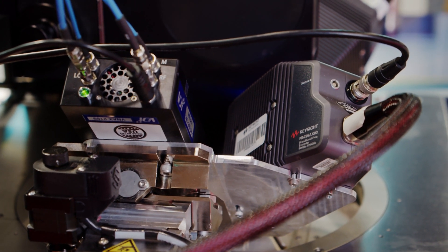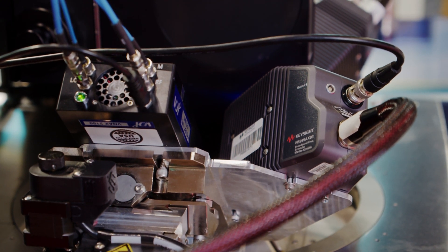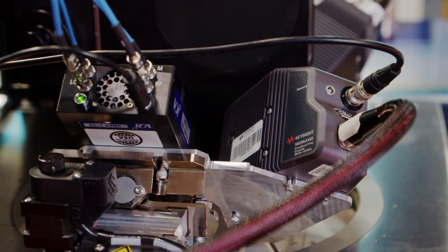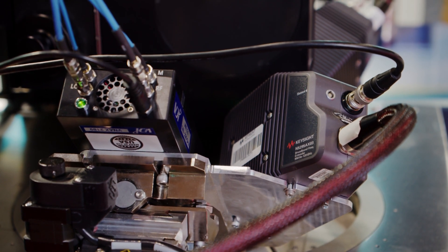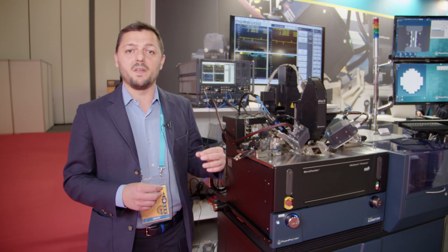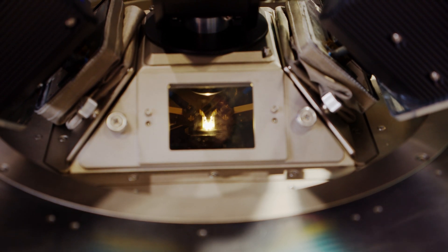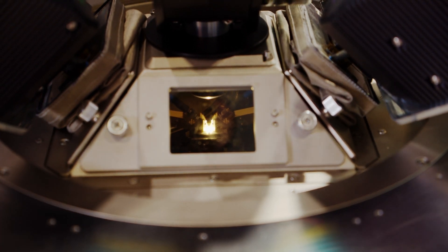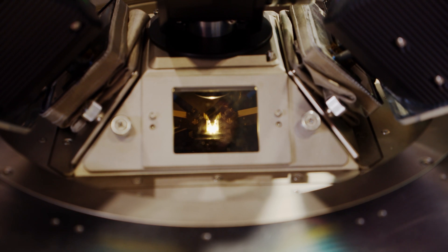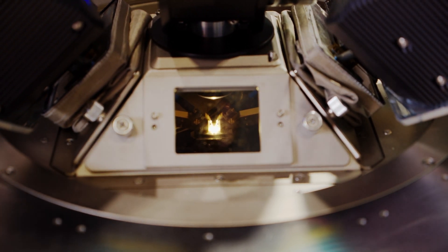The frequency extenders from Keysight go all the way up to 130 gigahertz, while the VDI frequency extender covers the frequency range from 130 all the way up to 220 gigahertz. The unique solution we developed together with Dominion Microprobe is a new probe that combines the two signals — the waveguide signal from the VDI extender and the coax signals from the Keysight N5291A — onto a single probe that lands onto the device under test on the probe station.